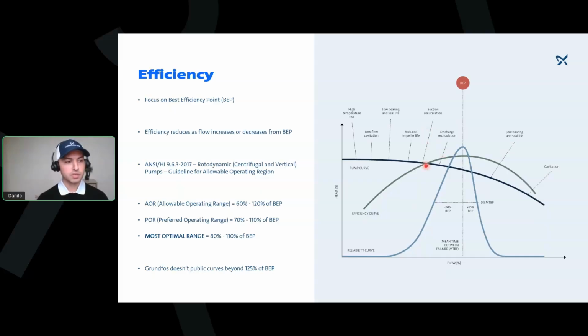Quoting the Hydraulic Institute, in 2017 they came out with pump guidelines for allowable and preferred operating ranges. So if you find your selection here, it tells you how far out to the right you're allowed to go and how far out to the left. You always want to be in the preferred operating range, the POR. You want to be from 70% to 110% of your best efficiency point.